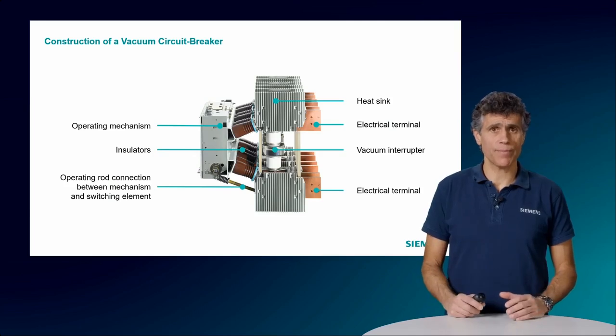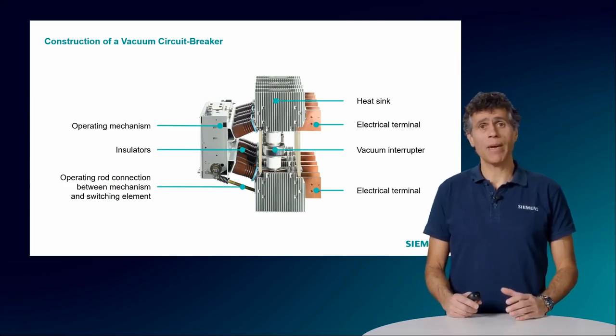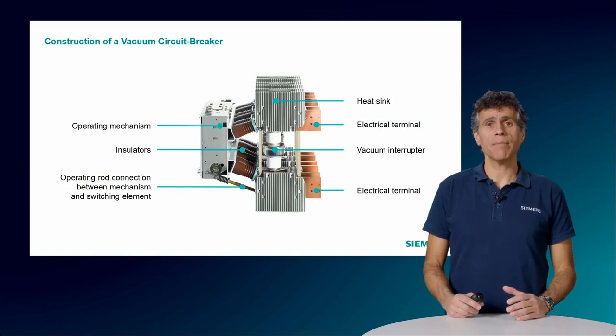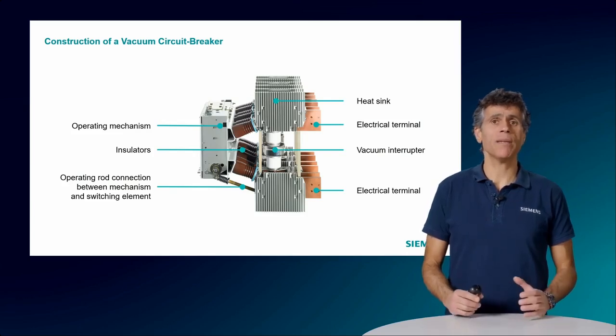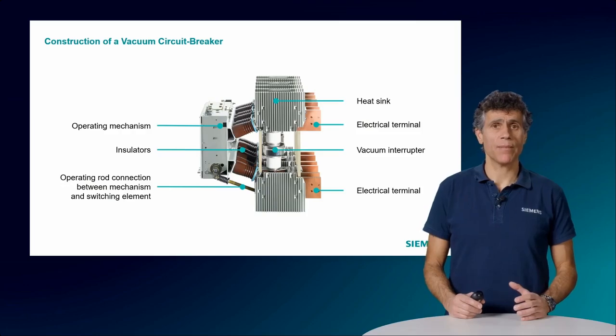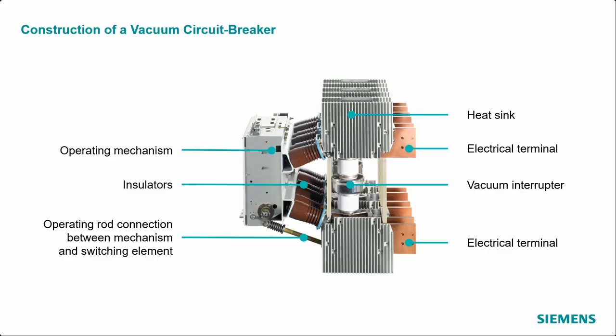fault recovery. Post insulators might be used or not, but the mechanism must be somehow insulated from the earthing potential. Any conductive path from the live parts to the earthed metalwork must be prevented. The insulators are used not only to withstand that high electrical stress, but must also withstand the strong mechanical forces acting on the breaker, which have the same nature as the forces we discussed before that act on the main busbar. High-quality insulators with a long lifetime are therefore a must.